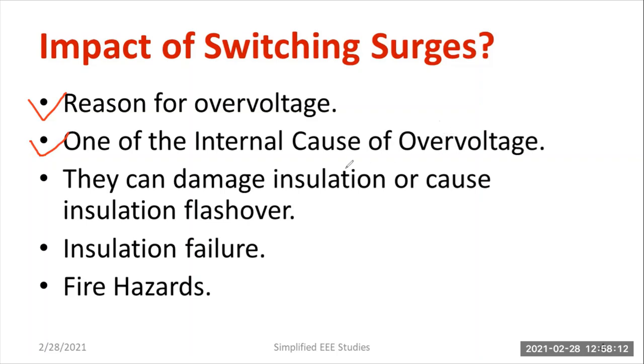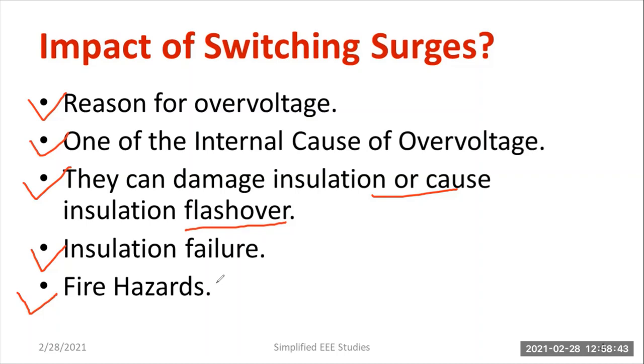We have studied external as well as internal causes of overvoltage. Switching surges can damage insulation or cause flashover — that will definitely take place, leading to insulation failure. For solid dielectric material, permanent failure will occur. For liquid or gaseous dielectric material, the failure will be temporary. It also causes severe fire hazards — as shown in the diagram at the beginning of the slides. These are the major impacts of switching surges.